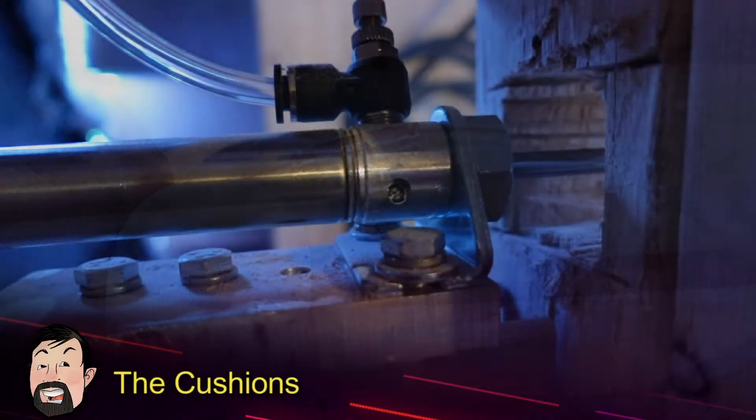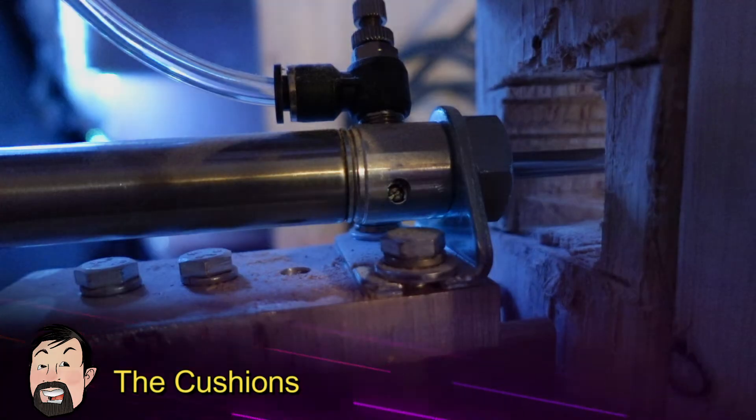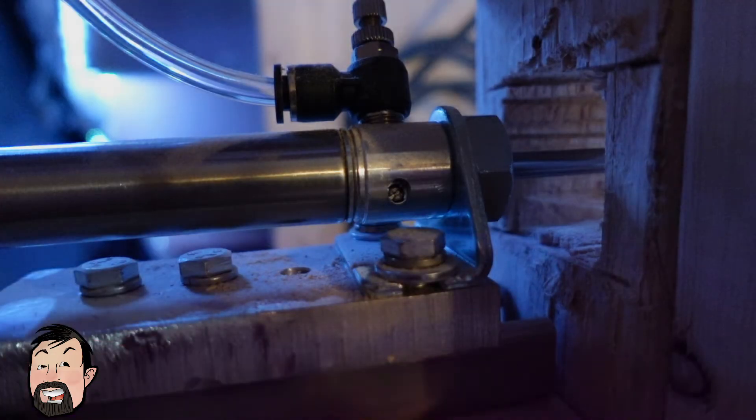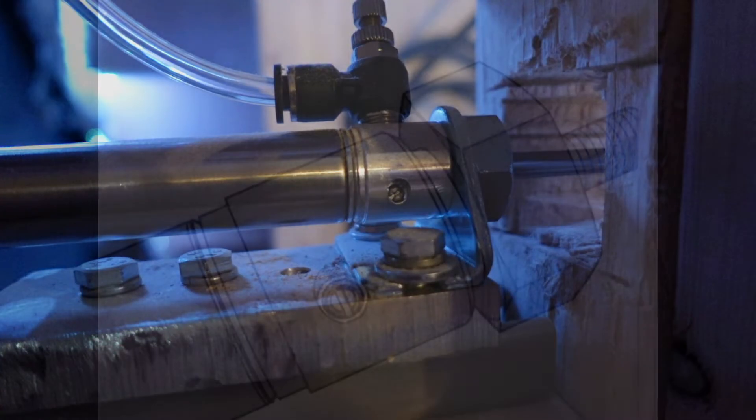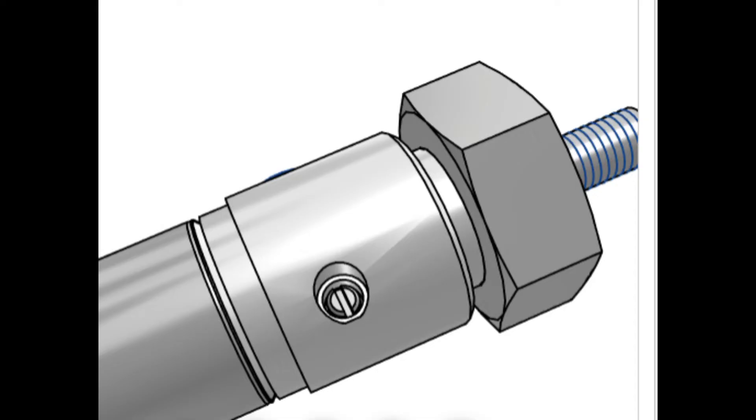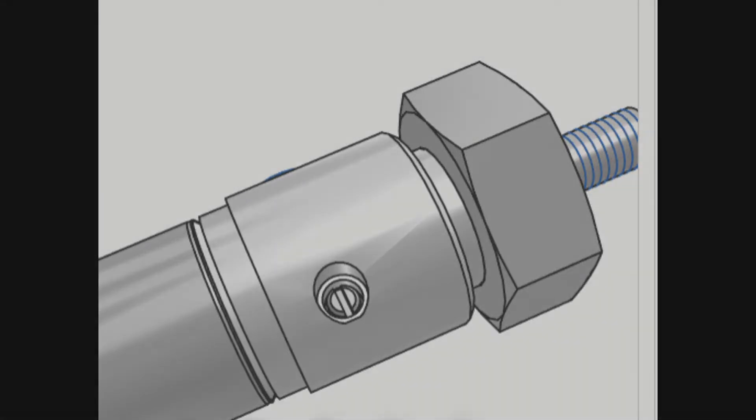I also wanted to talk about the cushions. The cushions are very important. If you don't use the cushions and you're looking for speed, you could destroy your cylinders. You could destroy your doors. It'll just kind of help you as it's like right at the end of stroke when it's about to finish closing or finish opening. It'll help it from not slamming. So it's very important for what you're looking for.